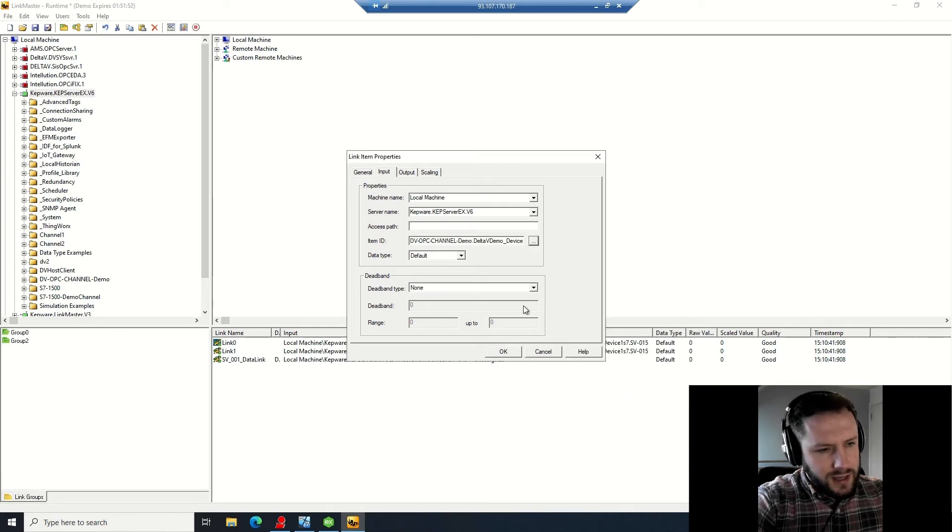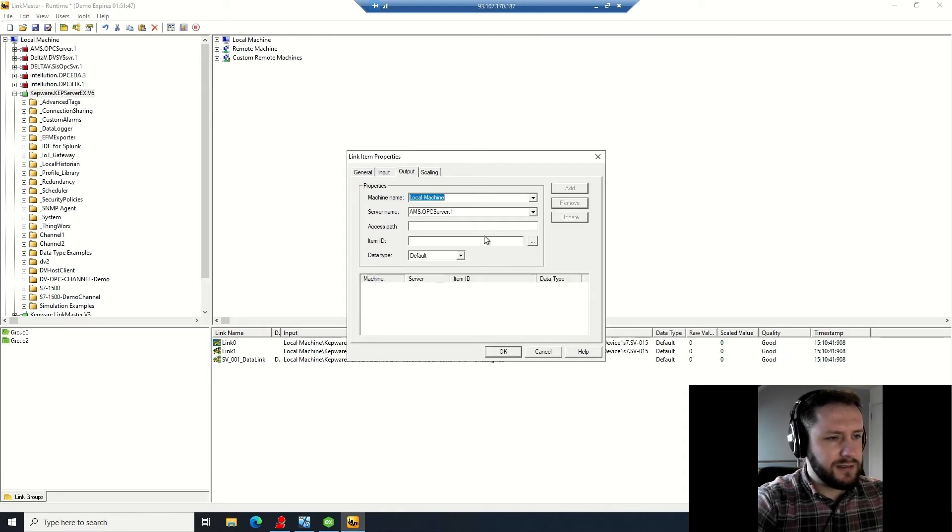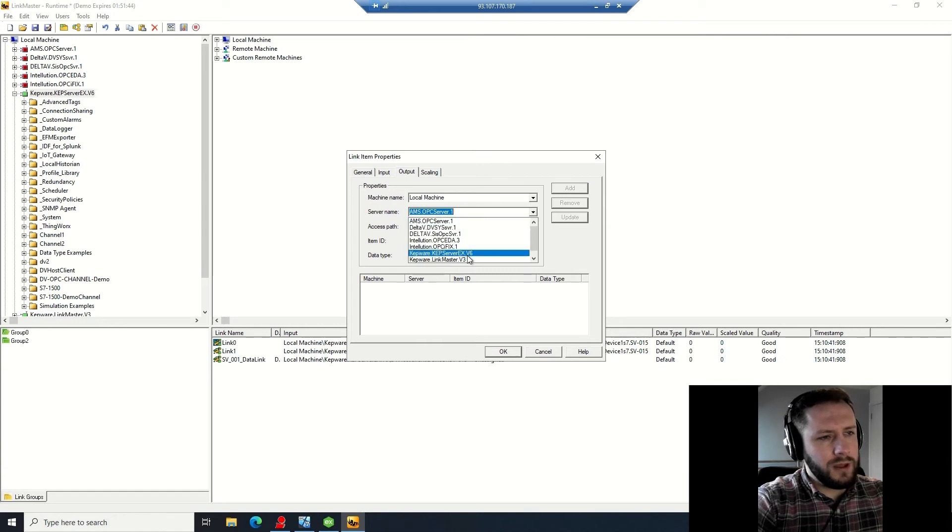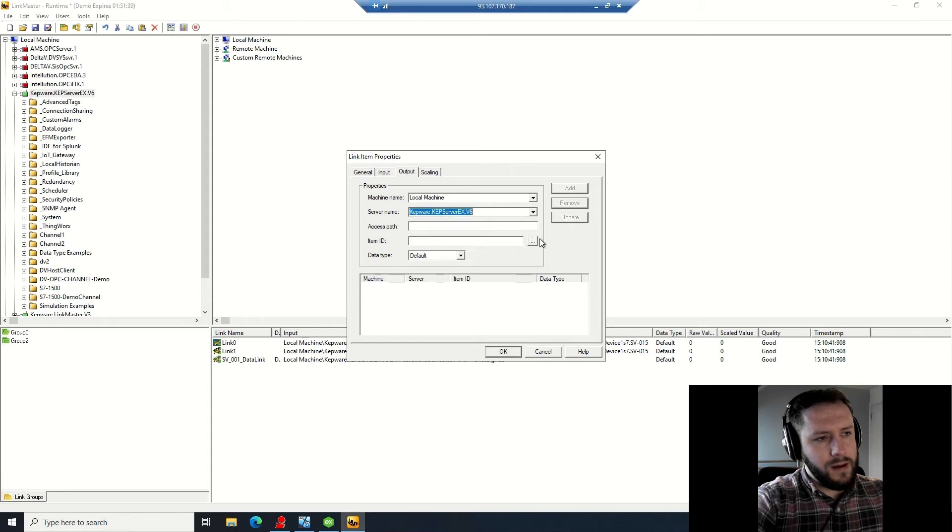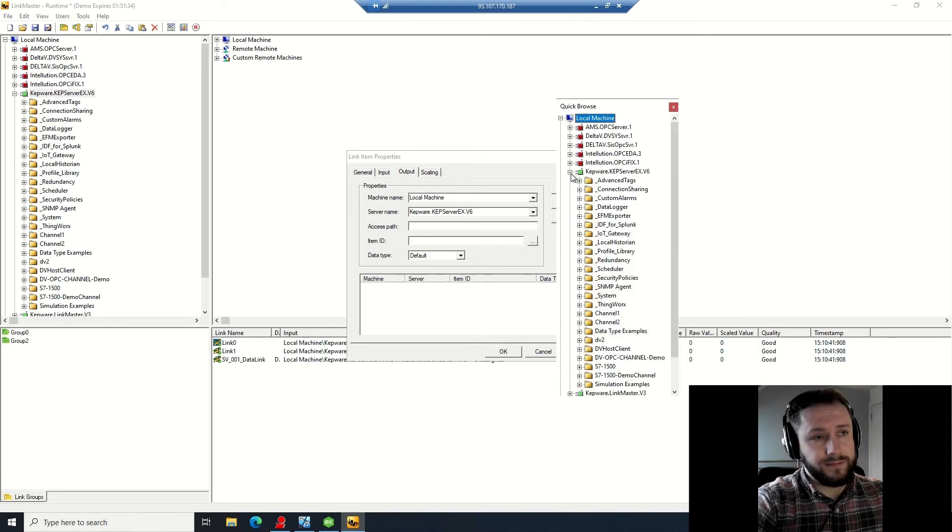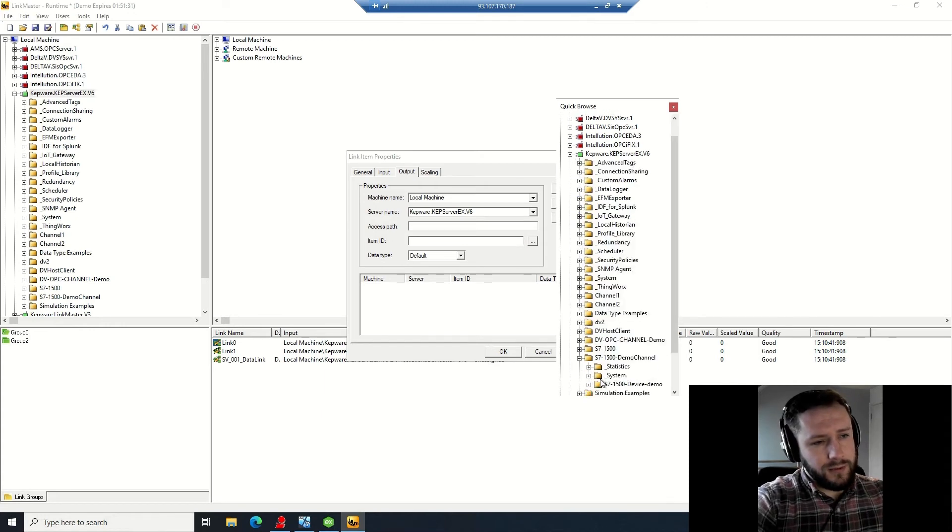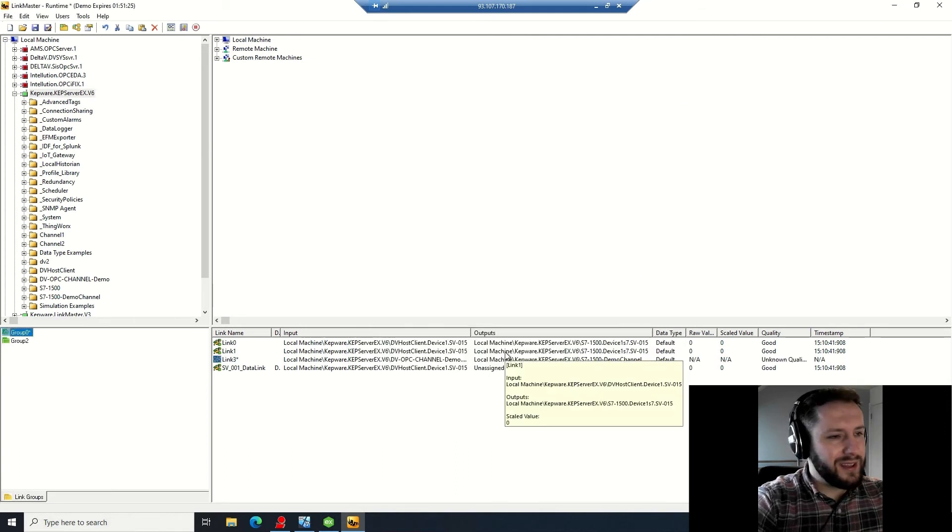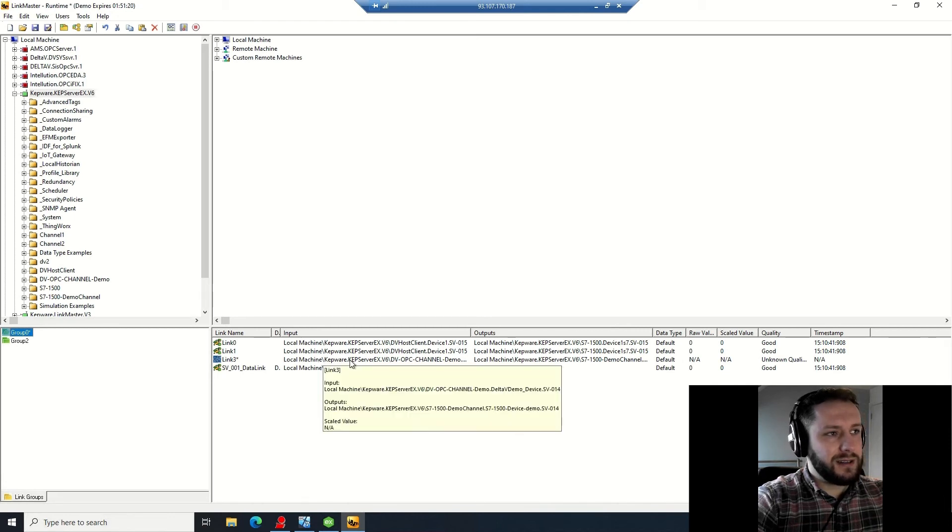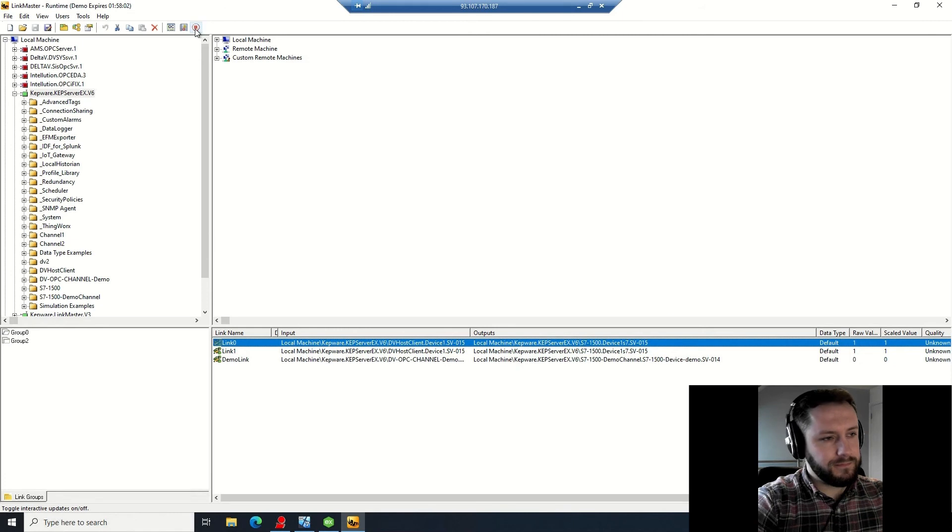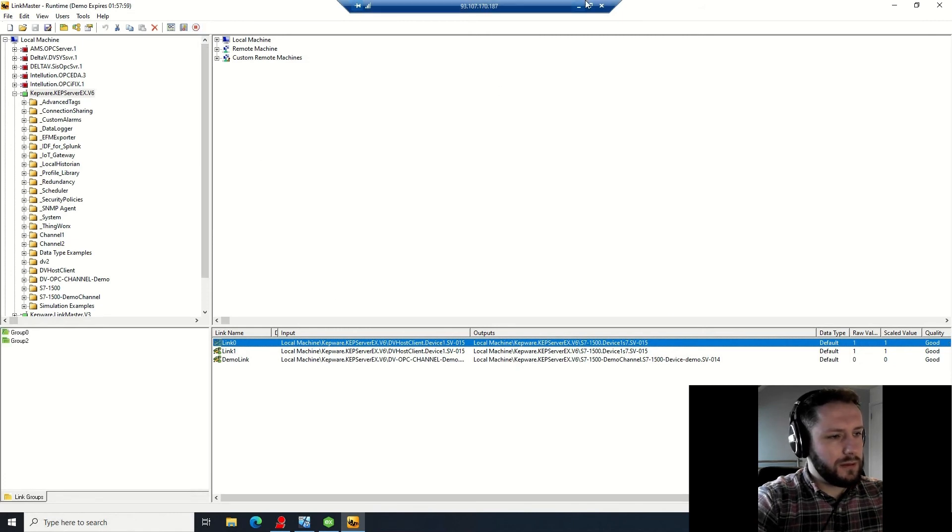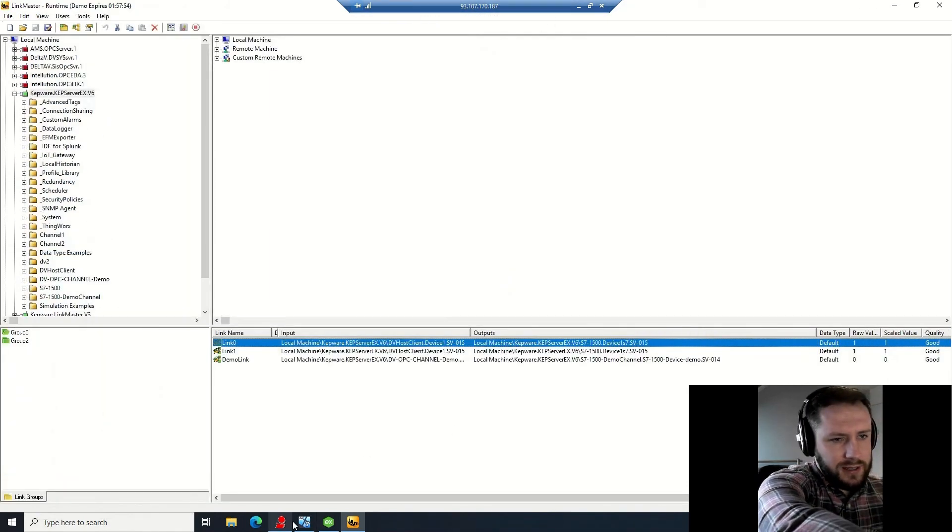So we should see SV014 - brilliant. And you can see there that it's linked to the Delta V signal. You want to go to output, you want to do the same, you want to reference the Kepware server, and then you want to browse to the tag for the Siemens device, which is in - I'm going to guess - S7 1500 device demo. Click OK. It'll come up there. Something you're going to have to come up to the top hand toolbar now and reinitialize by clicking the stop button, start it again. Great. I just deleted one of those tags there, and you can see there that demo link has an input value of zero currently.